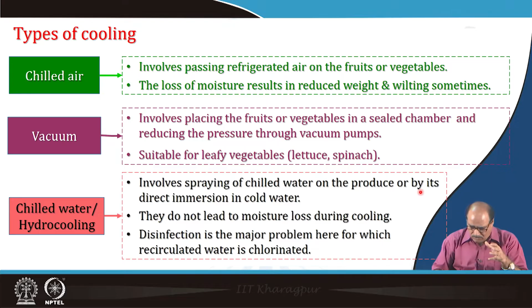Okay. Chilled air cooling: you can see in the figure here that exchange of heat is accomplished by changing the temperature of the air. Such temperature changes usually occur at constant pressure. The chilled air is passed inside the storage room or inside the package. There is an extraction fan which removes warm air from the cartons or storage environment. So, the amount of sensible heat change in the air may be estimated by Qs = m Cpa (T2 - T1), where m is the mass flow rate of the air, Cpa is the specific heat of air, and T2 minus T1 is the temperature difference between the outgoing air and incoming air.